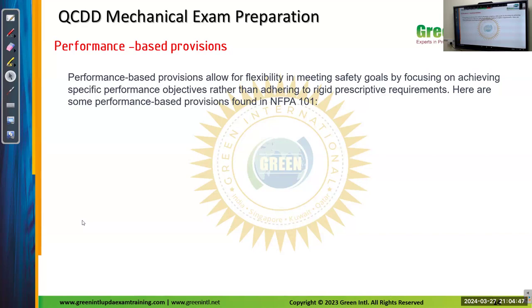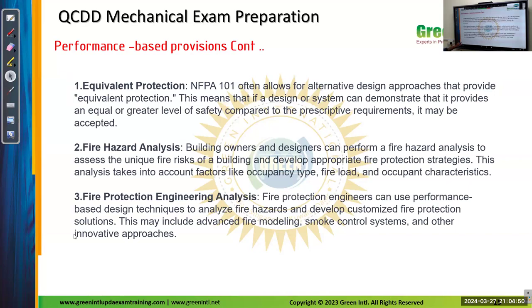Here are some performance-based provisions found in NFPA 101. Equivalent protection. Equivalent protection allows alternative design approaches that provide equivalent protection. If the design provides an equivalent or greater level of safety compared to the prescriptive requirements, it may be accepted. It means you are designing on your own. You are not following any of the standards, and you are proving that the system is working, meeting the requirements or more than the requirements. So it will be accepted. But you have to state that this is working properly. The time consumption for this process is more because you have to practically prove that.